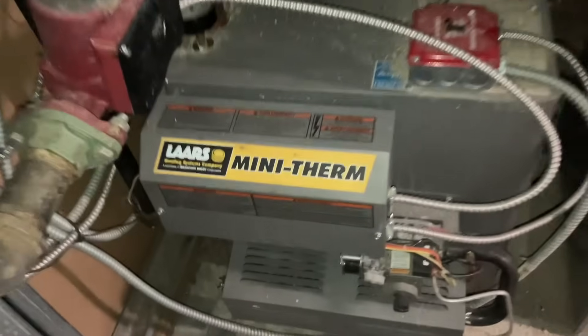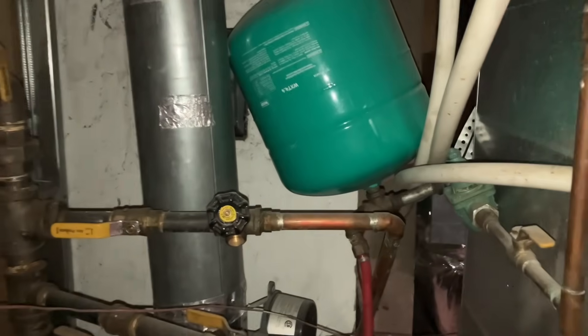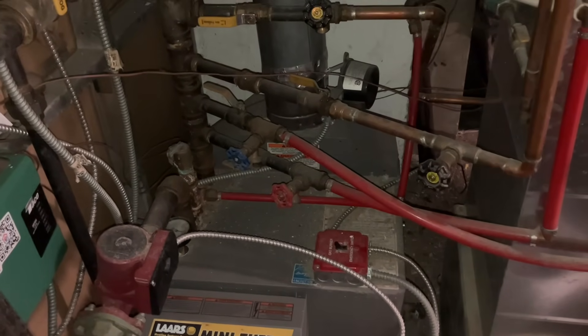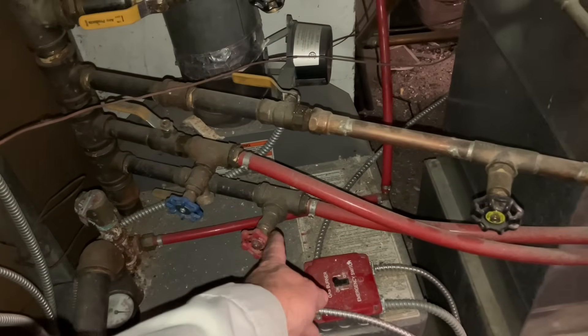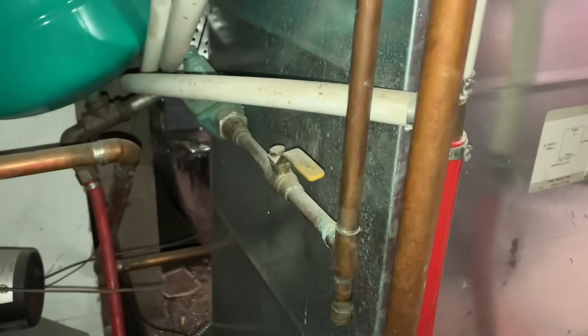Alright, I'm back at this Laars Mini-Therm. I've got to properly install that extra expansion tank and clean up this mess, including putting the drip leg on the relief valve. Where do we begin — this is just a disaster. Here's our domestic incoming water, let's close that off and isolate our zones.